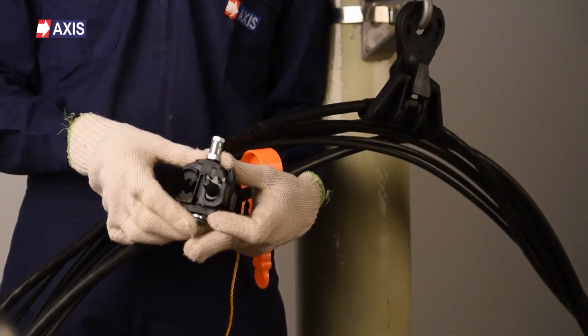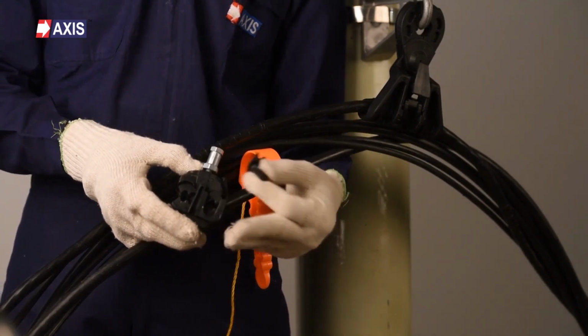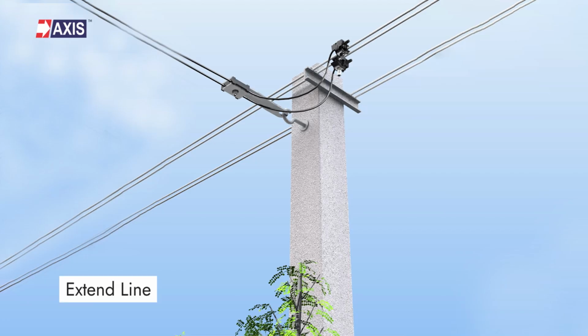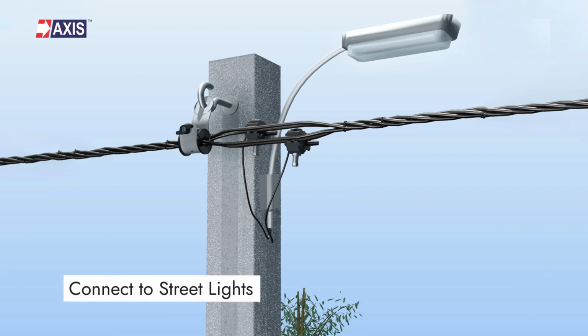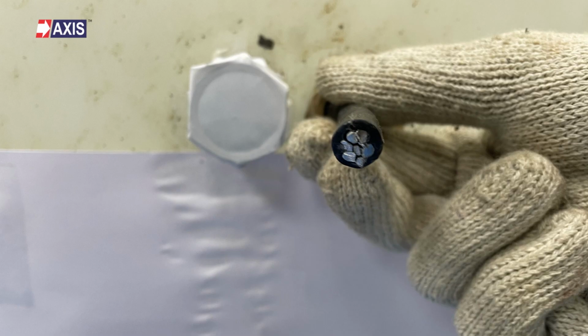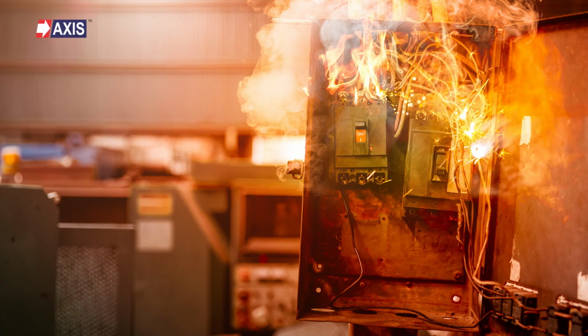Known as IPCs, insulation piercing connectors are used in all AB cable systems. They create tap connections that can extend the line, distribute the line, connect to street lights, or even connect to households. These connectors come with a water resistant design that seals the connection, guarding against water penetration. Low quality IPCs allow water to enter the cable, and this can cause issues like short circuits and metal corrosion that will compromise the entire electrical system.